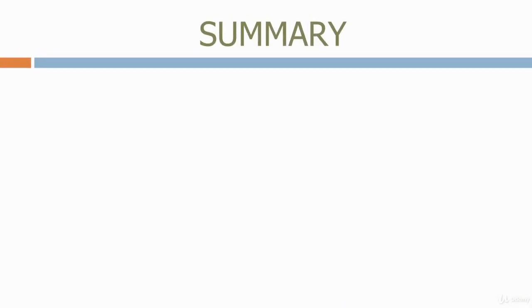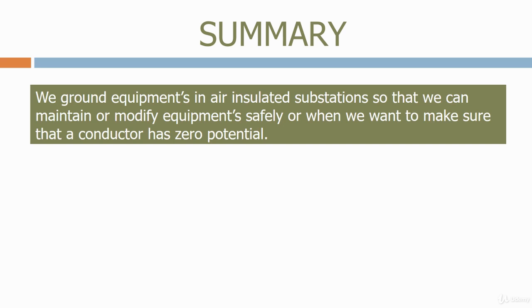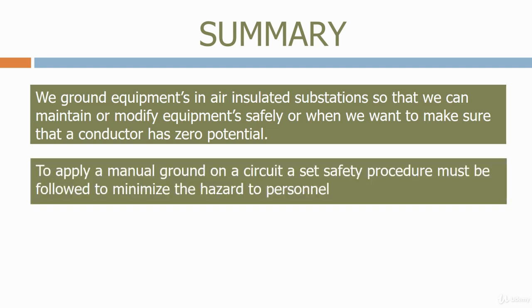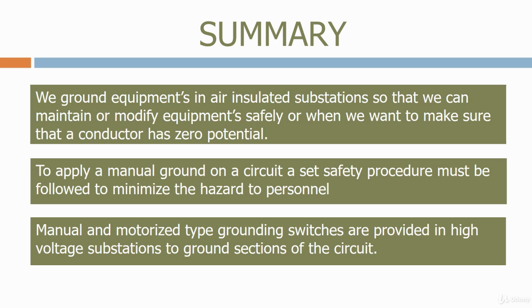Let's summarize what we've learned today. We ground equipment in air-insulated substations so that we can maintain or modify equipment safely, or when we want to make sure that a conductor has zero potential. To apply a manual ground on a circuit, a set safety procedure must be followed to minimize the hazard to personnel. Manual and motorized type grounding switches are provided in high voltage substations to ground sections of the circuit. You should now understand all about grounding equipment and how they are used to ensure personnel are kept safe whilst equipment is being installed, modified and maintained.